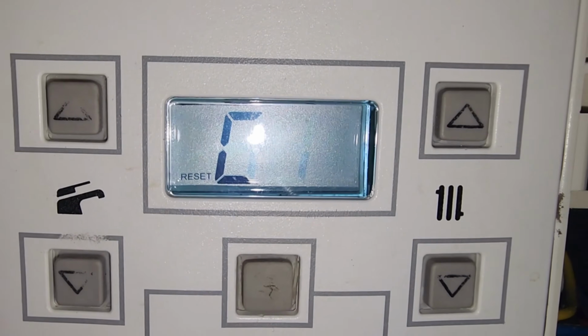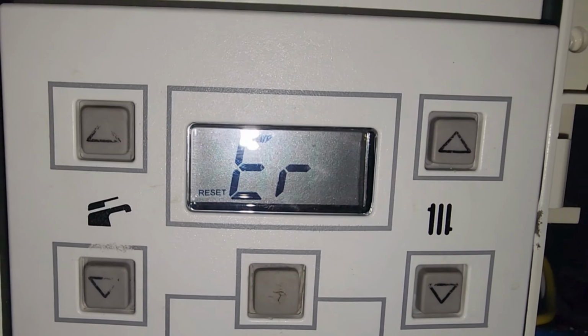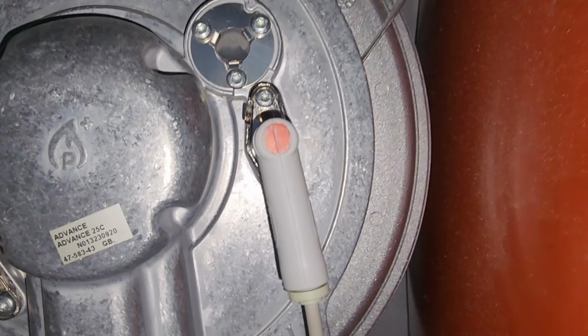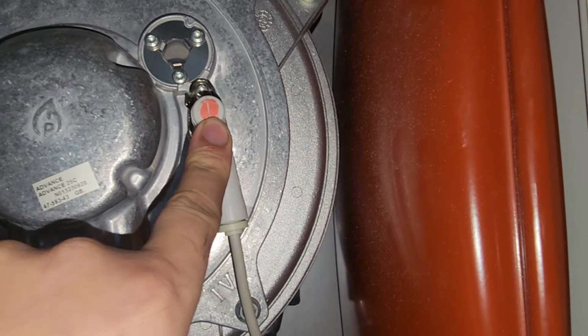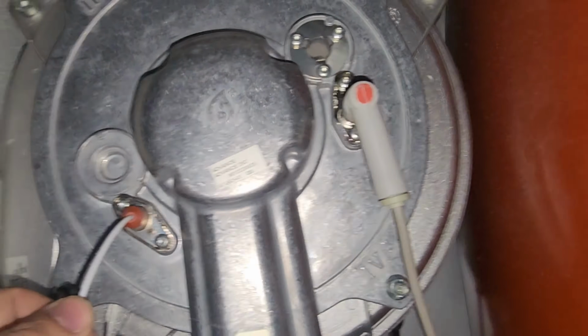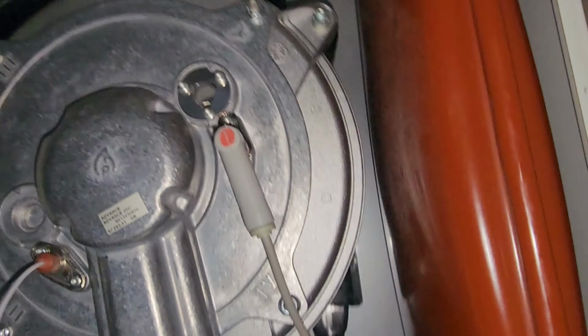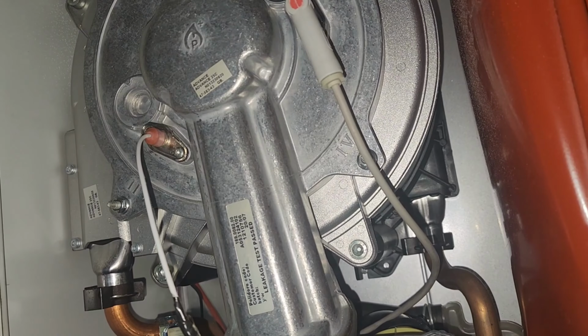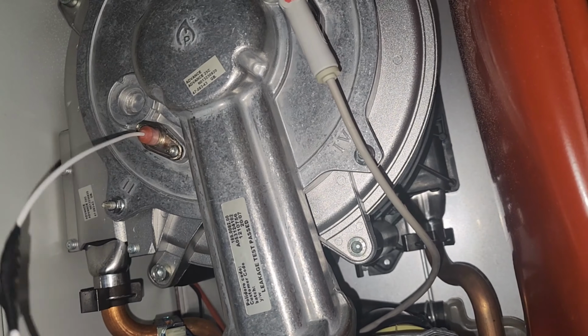So basically the burner is sparking and igniting, but it's not holding flame. The reason is that this part here is not detecting the flame, so we're going to have to change it.